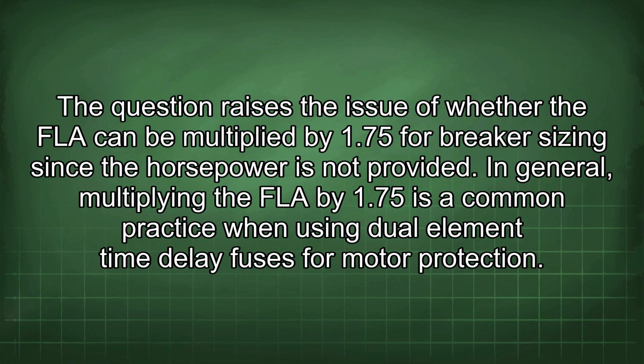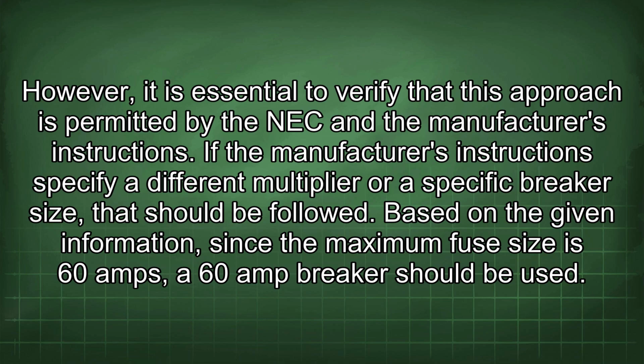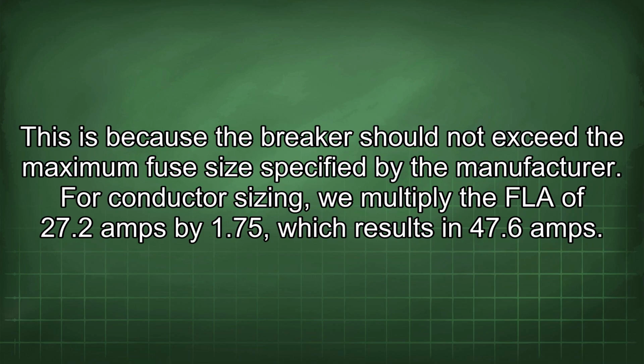fuses for motor protection. However, it is essential to verify that this approach is permitted by the NEC and the manufacturer's instructions. If the manufacturer's instructions specify a different multiplier or a specific breaker size, that should be followed. Based on the given information, since the maximum fuse size is 60 amps, a 60 amp breaker should be used. This is because the breaker should not exceed the maximum fuse size specified by the manufacturer.